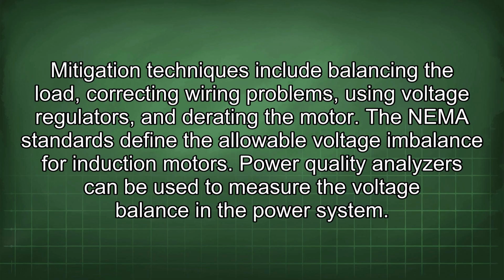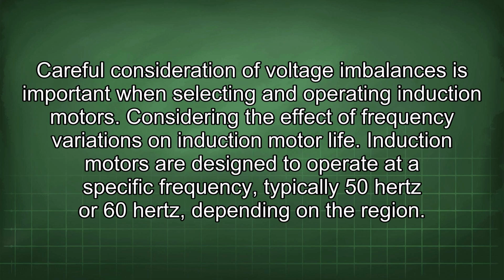Mitigation techniques include balancing the load, correcting wiring problems, using voltage regulators, and derating the motor. The NEMA standards define the allowable voltage imbalance for induction motors. Power quality analyzers can be used to measure the voltage balance in the power system. Careful consideration of voltage imbalances is important when selecting and operating induction motors.